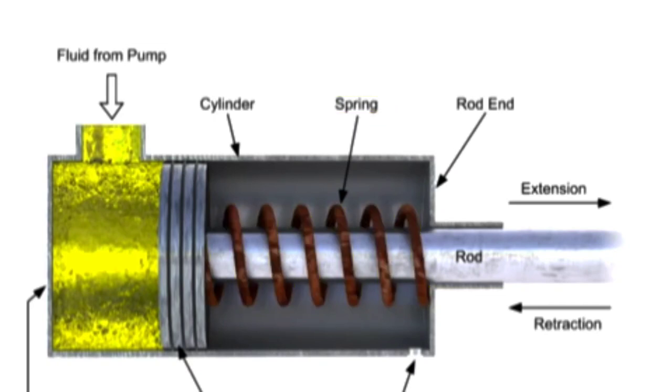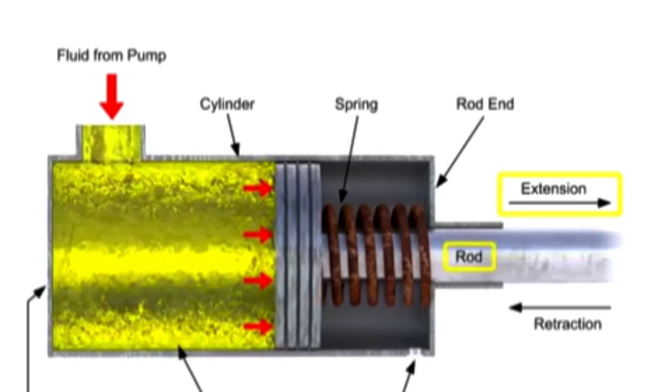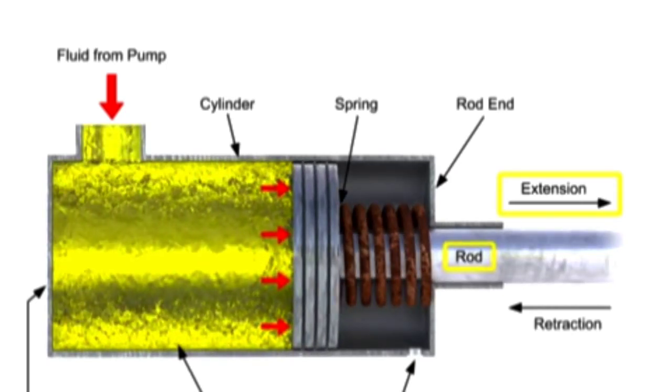A single-acting cylinder produces linear motion in one direction. When a control valve directs fluid through the inlet port into the blind end, pressure builds up and generates a force on the piston. When the pressure build-up is large enough, the piston begins to move, extending the rod. This is called the forward stroke.